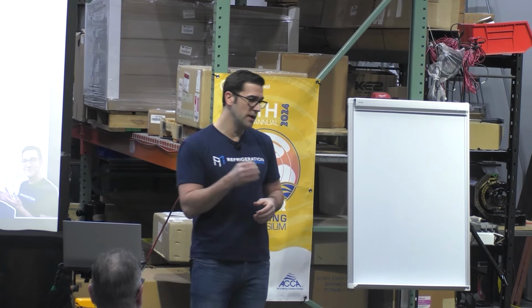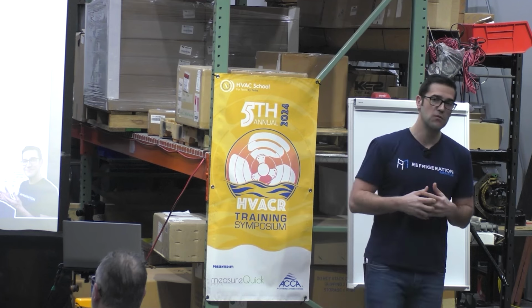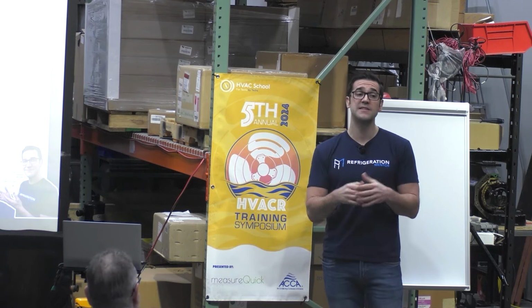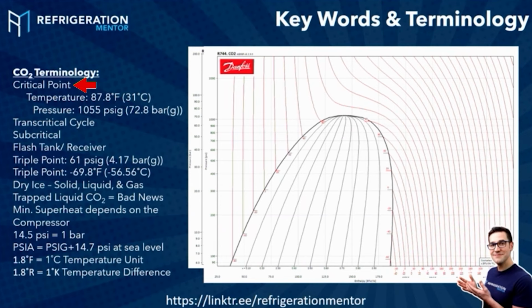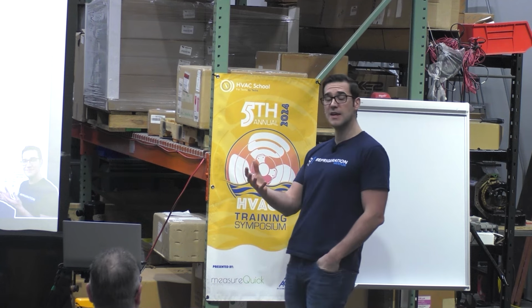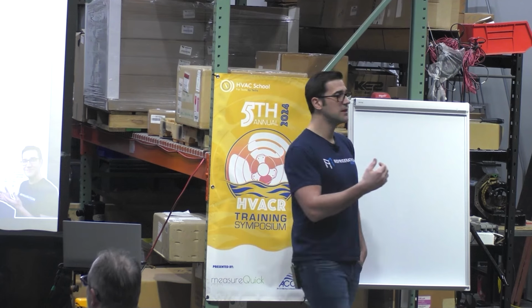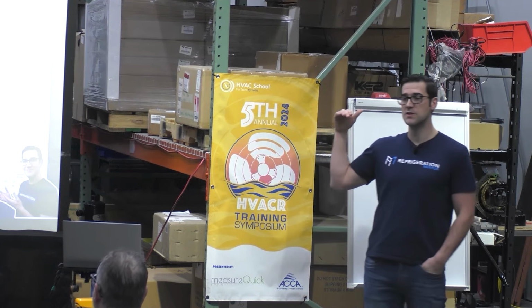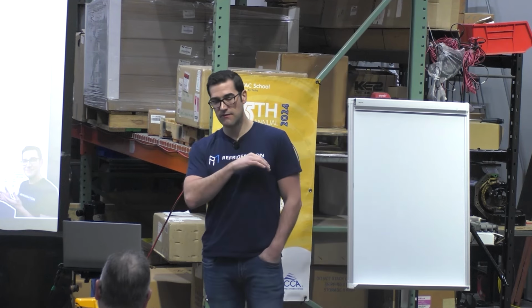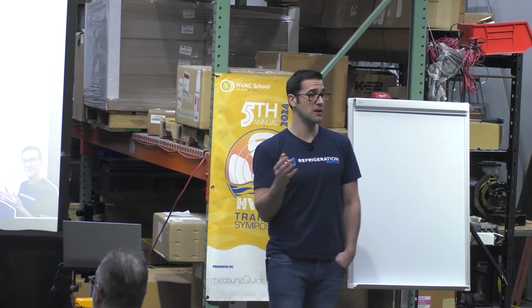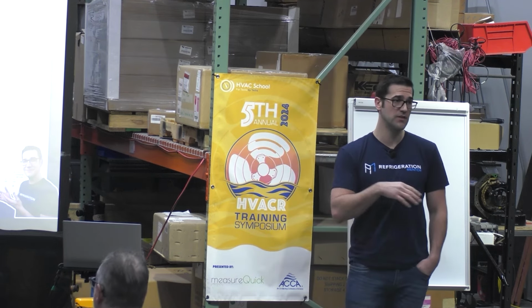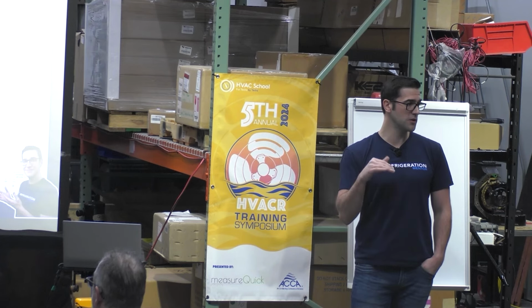So terminology, there's one key term that you need to know, and that we really started to talk about more with CO2, and that's the critical point. Does anybody know what the critical point is? Or where it is on this diagram, we'll say. So right there, that's the critical point. Every refrigerant has a critical point. But since CO2 came out, now we're talking about the critical point. And what do you think the critical point means? So below this critical point, we're in subcritical. And that's how every system out there, doesn't matter what system, you talk about a chiller, AHU, VRF, VRV, we're in subcritical. We're below the critical point.